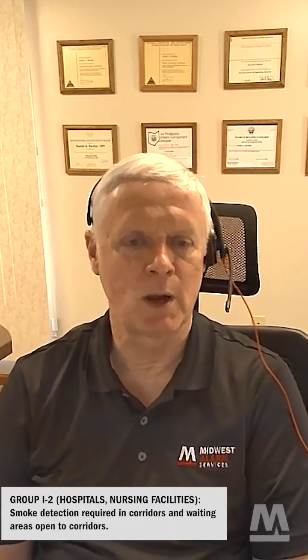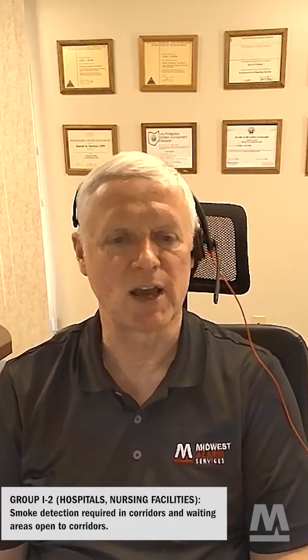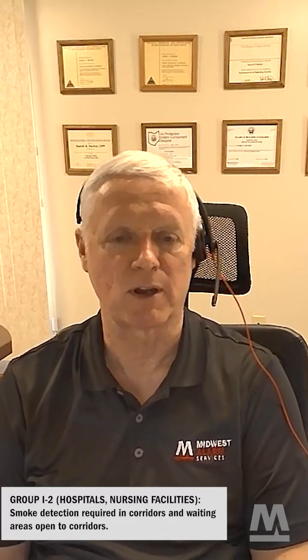Getting into Group I2, hospitals and nursing facilities, smoke detection is required in corridors and waiting areas open to the corridors, but then it has an exception that says smoke detection is not required in smoke compartments containing sleeping units where a visual display is provided on the corridor side of each sleeping unit and an audible and visible signal is provided at the nurse's station. Also not required where doors are equipped with automatic door closing devices with integral smoke detectors that perform the required alerting function. And those are pretty much gone today. The last time I saw door closers with integral smoke detectors in them, the devices were like 30 years old and are being replaced, and they don't have a replacement device for them other than to add spot detectors and replace the door holder.